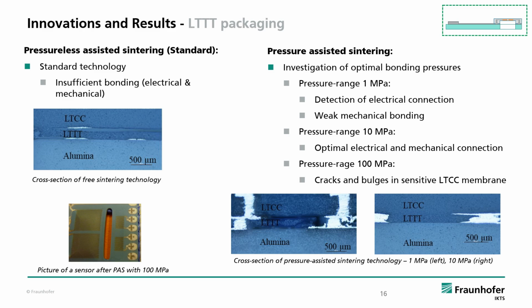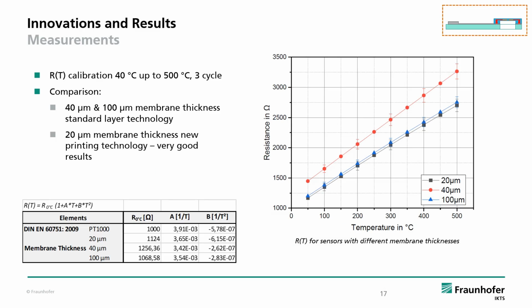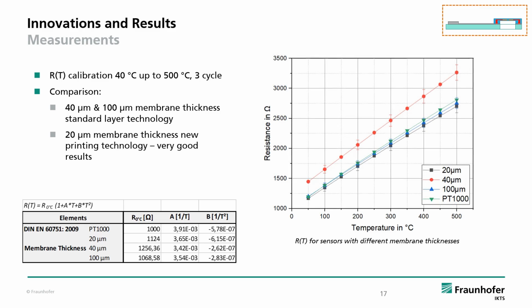So after finding the optimal process parameters, it is possible to measure the sensors. We started with a resistance over temperature curve with the different membrane thicknesses up to 500 degrees. Here you can see the results compared to the PT1000 curve. The 20 micron and 100 micron membranes show an excellent fit to the curve. On the other hand, the 40 micron membrane has a much higher drift. The reason can only be found in the different fabrication process, since all materials are the same in all processes. And as you can see in the diagram, the printed membrane shows very good results.